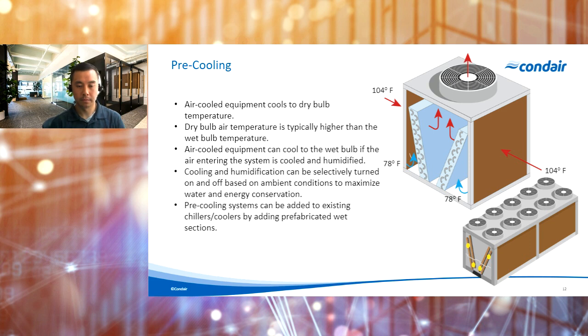So if we look at this diagram on this page, it's representative of something like an air-cooled chiller, with the blue being the condenser coils and brown being the adiabatic cooling media. For example, if this application had air with a dry bulb of 104 degrees and a wet bulb around 70 degrees Fahrenheit, the adiabatic media could cool the air to around 78 degrees. So this would allow the system to be cooled with air that's about 26 degrees colder. The use of pre-cooling can also be set to only turn on under certain conditions, allowing for an optimized use of both power and water at the facility.